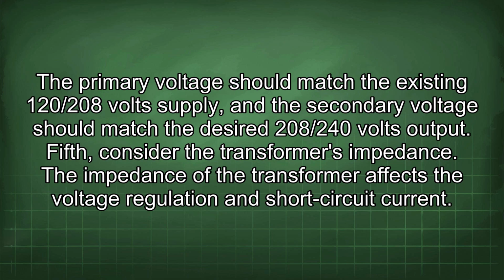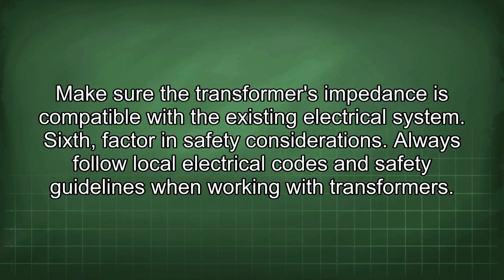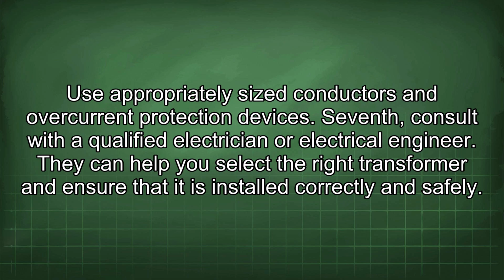Fifth, consider the transformer's impedance. The impedance of the transformer affects the voltage regulation and short-circuit current. Make sure the transformer's impedance is compatible with the existing electrical system. Sixth, factor in safety considerations. Always follow local electrical codes and safety guidelines when working with transformers. Use appropriately sized conductors and overcurrent protection devices. Seventh, consult with a qualified electrician or electrical engineer. They can help you select the right transformer and ensure that it is installed correctly and safely.